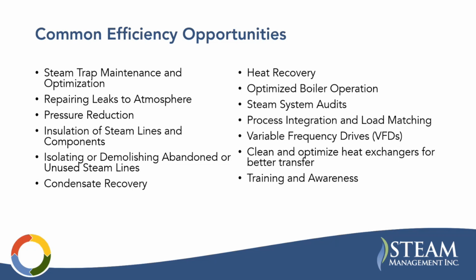Insulation is a good opportunity. Obviously, anything that's uninsulated is wasted heat. Most of the components in your steam system could do to be insulated, with the exception of condensate tanks, where you have to think it through, as insulating those can cause cavitation issues in the pump. But anyway, that's another one. Isolating or demolishing abandoned or unused steam lines. Like we're talking about with the pressure reduction, just having sprawling systems of lines that really aren't being used anymore is a big waste. You're getting waste through your steam traps, your pipe walls thermally, leaks, as well as simmering safety relief valves. It's just a lot of loss that could be avoided.